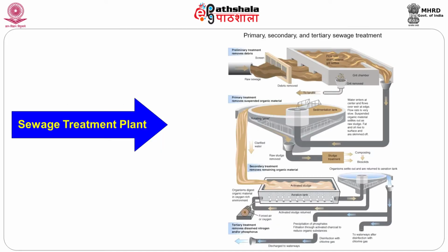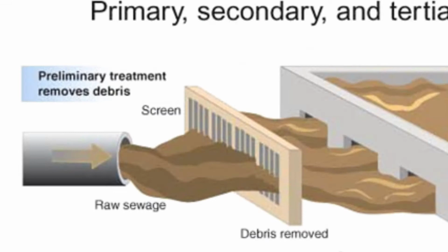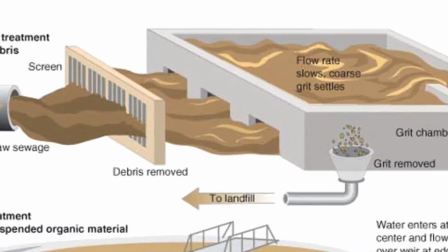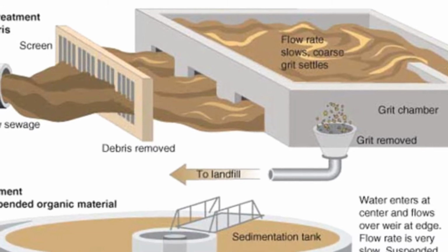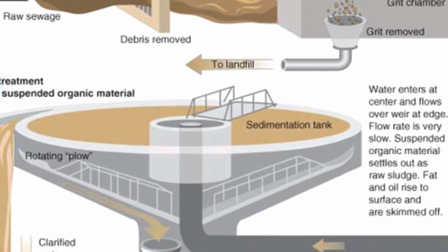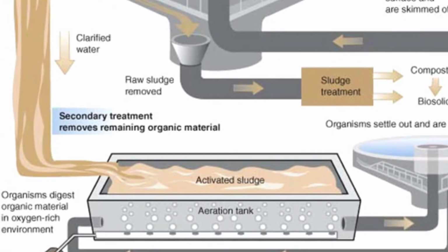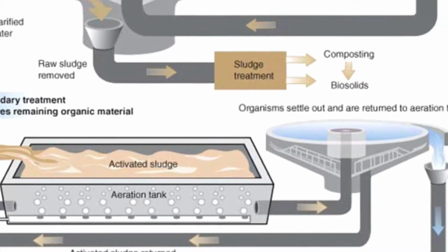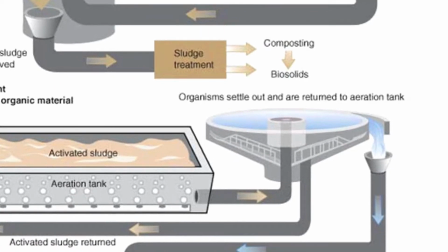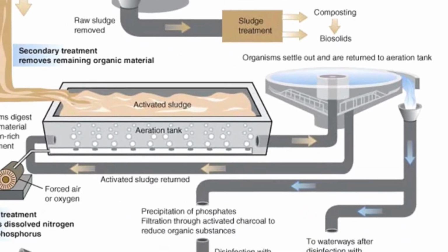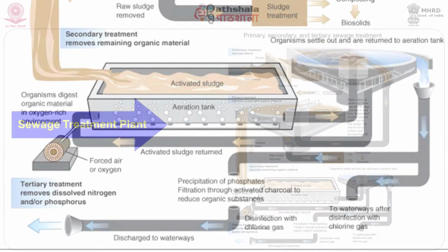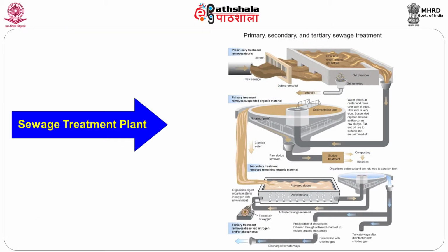So, this is another scheme we have. Here, raw water is fed into the bar screen, where we are trying to remove rags and other bigger particles. Subsequently, we have a grit chamber to remove grit particles present in the feed stream. Subsequently, we feed the effluent into the primary clarifier, which is operated in an upward manner, and the flow pattern is radial outflow. The clarified effluent is fed into the aerobic reactor. Subsequently, we have one more solid-liquid separator at the downstream side of the aeration tank. The sludge collected in the secondary clarifier is sent back to the aeration facility in order to maintain the MLSS population at a constant rate. In addition to that, we have a sludge removal facility.